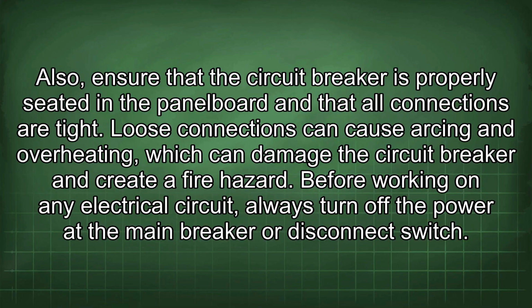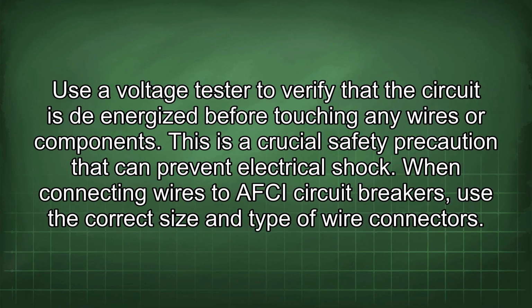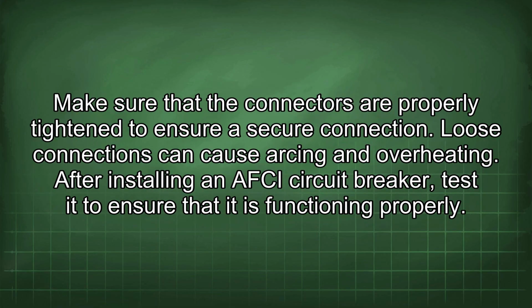Before working on any electrical circuit, always turn off the power at the main breaker or disconnect switch. Use a voltage tester to verify that the circuit is de-energized before touching any wires or components. This is a crucial safety precaution that can prevent electrical shock. When connecting wires to AFCI circuit breakers, use the correct size and type of wire connectors. Make sure that the connectors are properly tightened to ensure a secure connection. Loose connections can cause arcing and overheating.